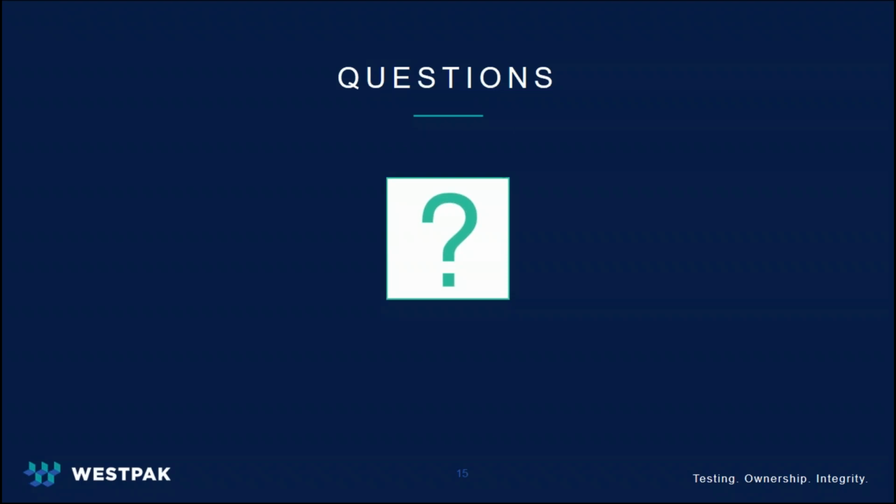Okay, and Greg, for those people in the audience who may not know, could you explain a little more about that term, IQ, OQ, PQ? Oh, yeah, sure, Tim, no problem. So IQ, OQ, PQ is installation qualification, operational qualification, and performance qualification, and you do that when you're doing a sealer validation. So you'll install it, make sure it works, make sure it operates correctly, and make sure it performs the way you want it to. And you would do a validation and a validation report at the end of that.